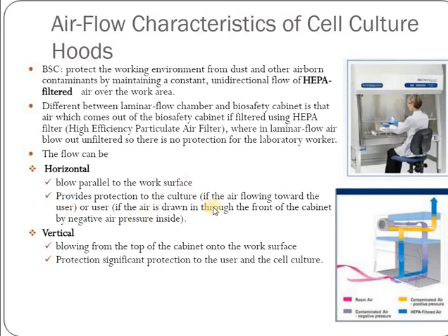It provides protection to the culture if the air is flowing towards the user, or to the user if the air is drawn in front of the cabinet by negative air pressure inside. Vertical flow blows from the top of the cabinet into the workspace. Significant protection is provided to the user and the cell culture.